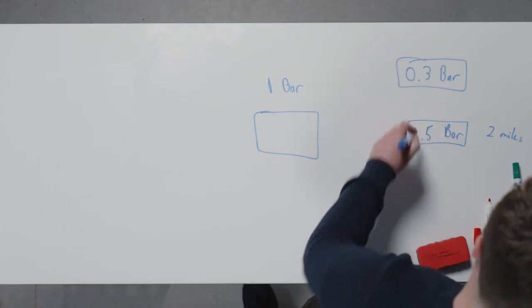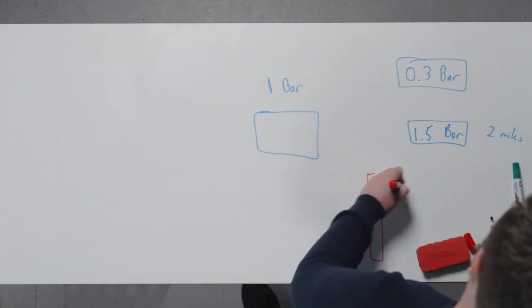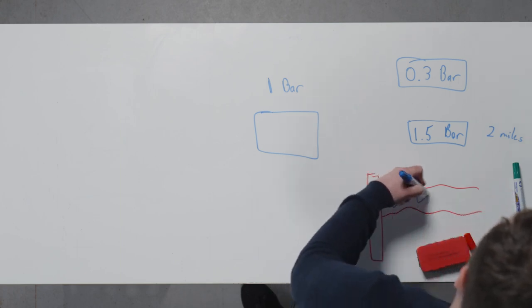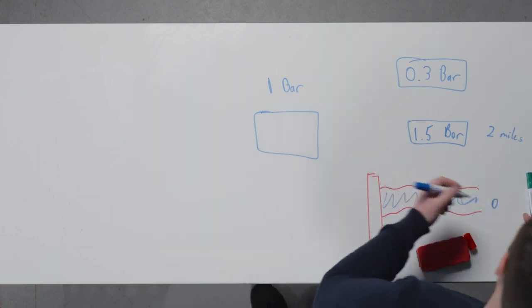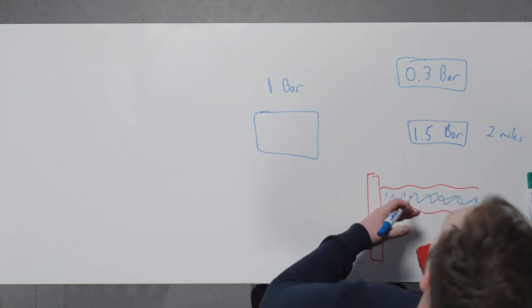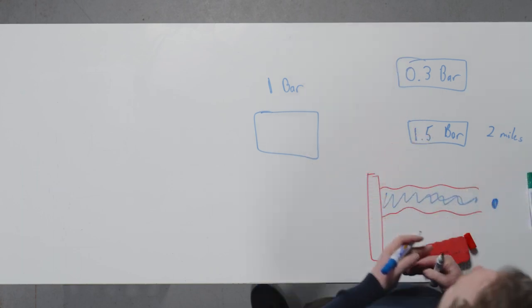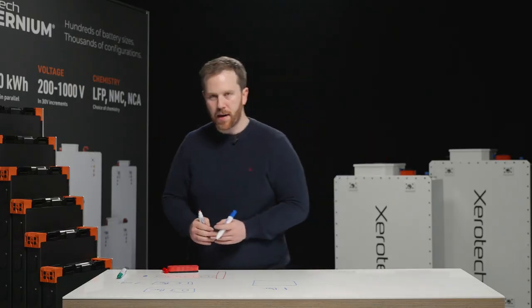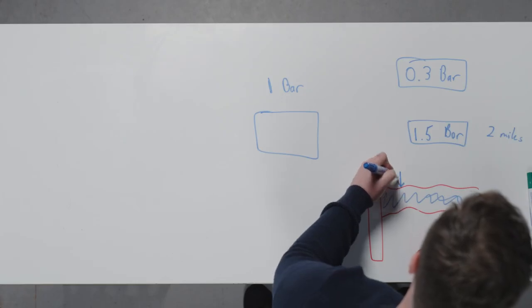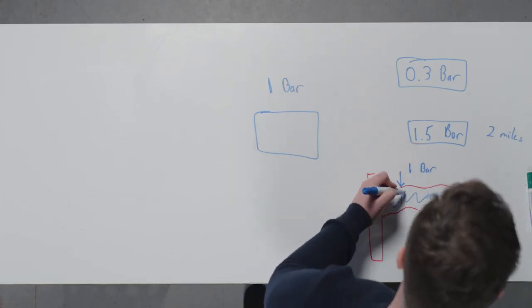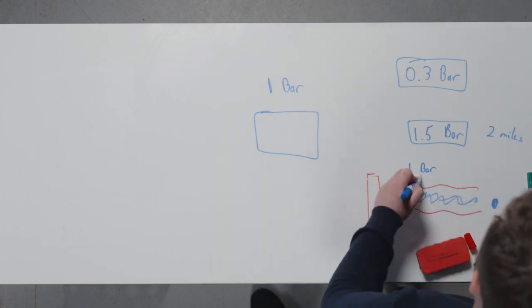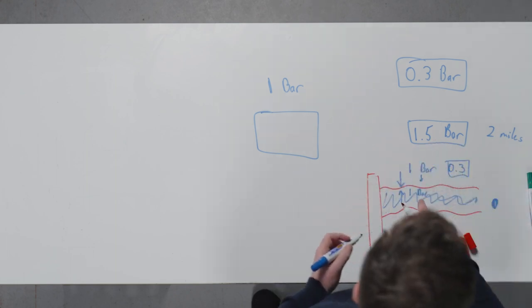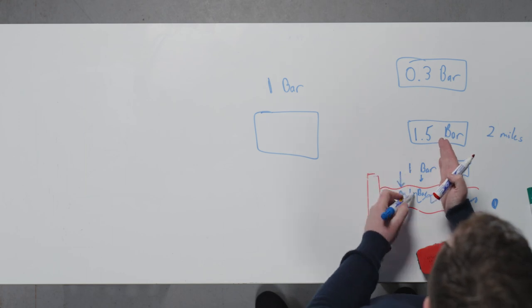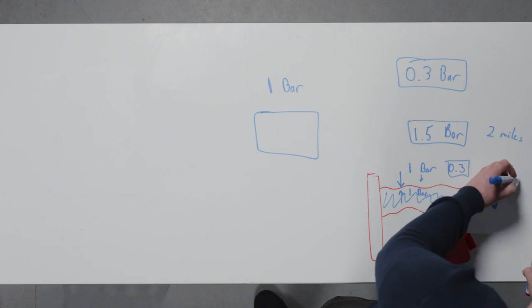So the reason this is important is if we go back to our duct cooling system, and we've got our ducts going through here, and if we have water in this duct and we start at sea level and we're just sitting here at ambient pressure, so it's effectively 0 bar gauge, it's just the standard ambient pressure. If we go high in the air, this will actually expand. So if you go up with a balloon to the top of a mountain, the balloon will get bigger. Not because you're increasing the pressure in the duct, it's because at sea level, you've got 1 bar pushing this way, 1 bar pushing this way. As you go higher, this number gets lower. It'll drop down to 0.3 bar. So actually the net pressure here is going to be at sea level, 1 minus 1, 0. It's an equilibrium. But as you go higher, it's actually going to gain 0.7 bar of differential pressure. And that's what we care about.